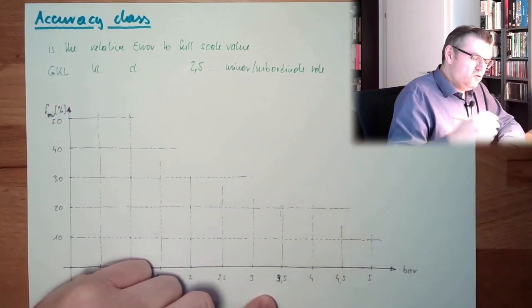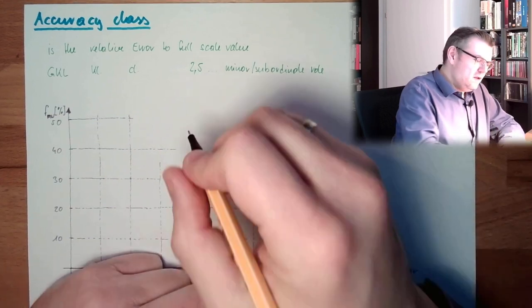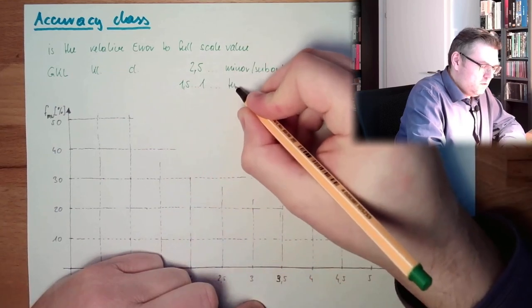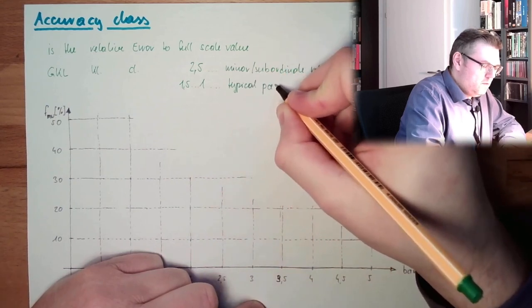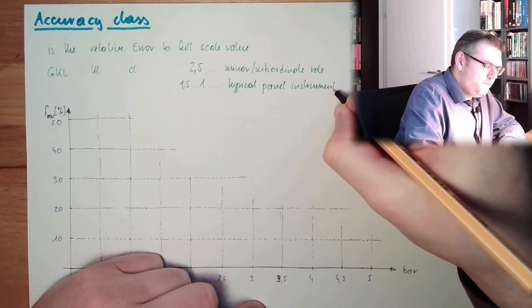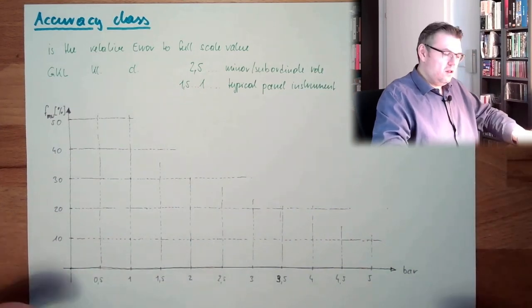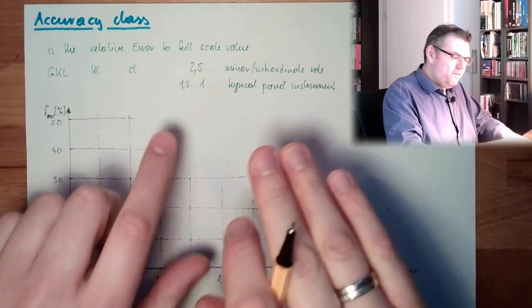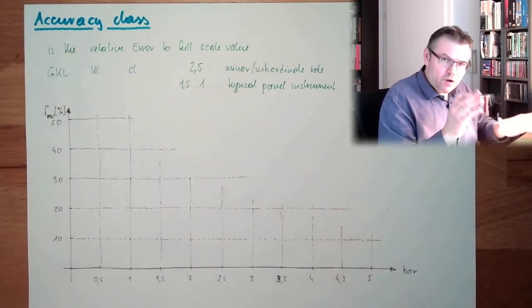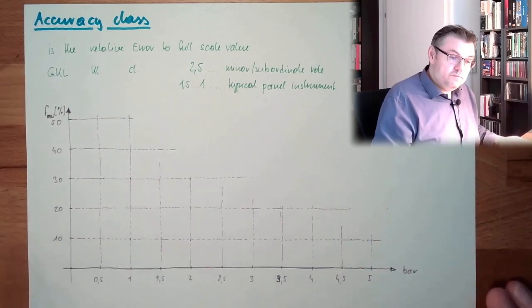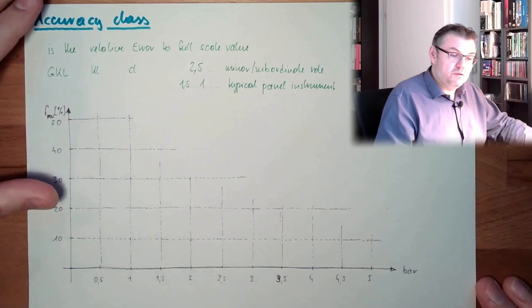Typical panel instruments, they have between 1.5 and 1, 1.1. So if you have somewhere operator panel, and there are instruments inside, then they are usually class 1, 1.5, something like this. So 1% of the full-scale value error, 1.5% of the full-scale value error.